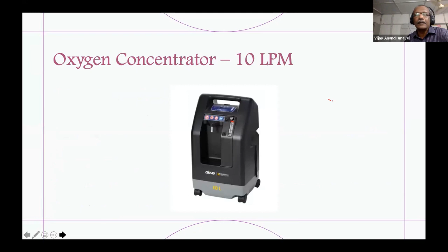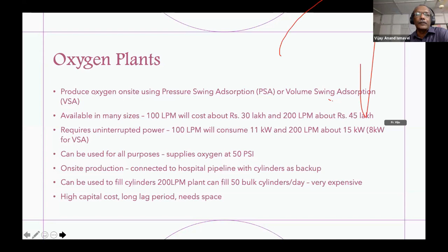So this is the cost. A 100 liter per minute oxygen plant is approximately 30 lakhs, probably much more now during the COVID period. And it will consume about 8 to 11 kilowatts of power. Again, you need uninterrupted power. And 200 liters per minute is 45 lakhs and 15 kilowatts. These plants can also be used to fill cylinders, but that is very expensive because from 50 psi you have to increase to 2000 psi. So a plant for filling 50 bulk cylinders per day will probably cost about 1 crore rupees.